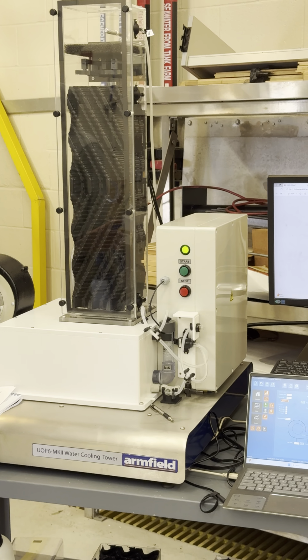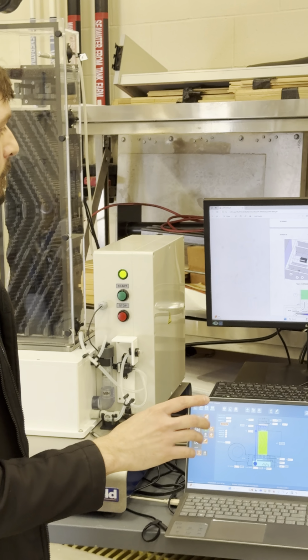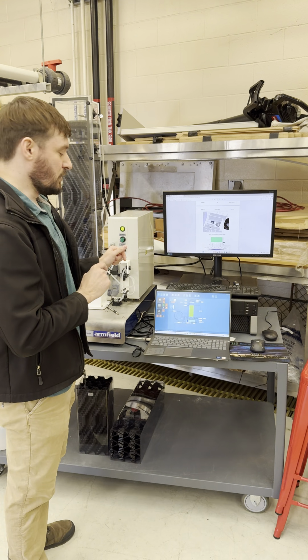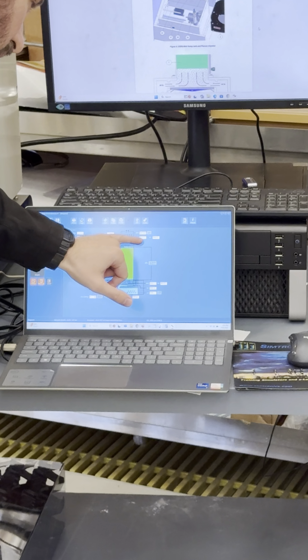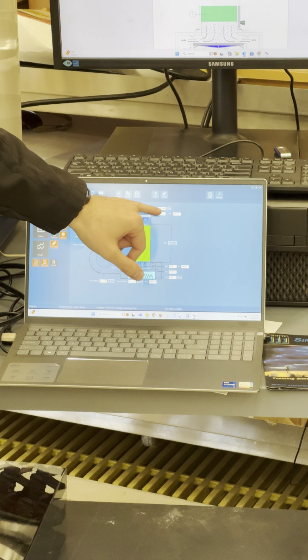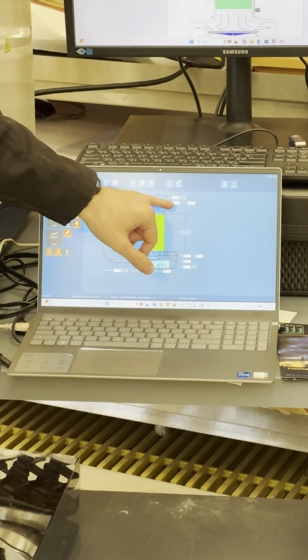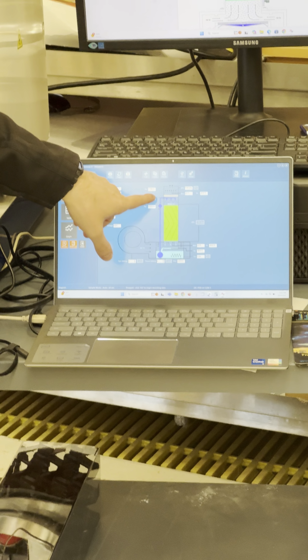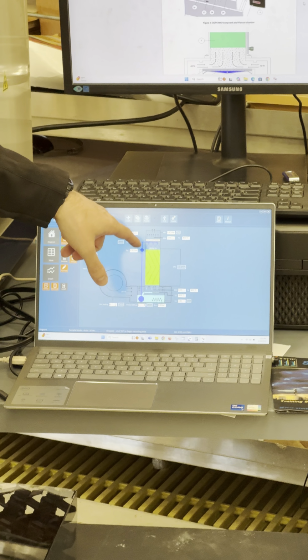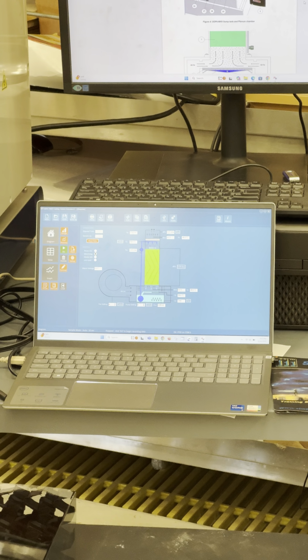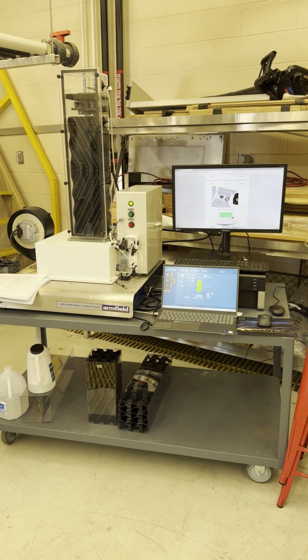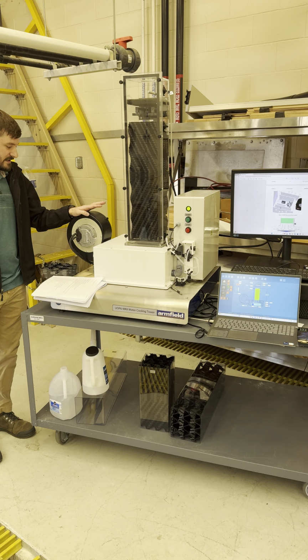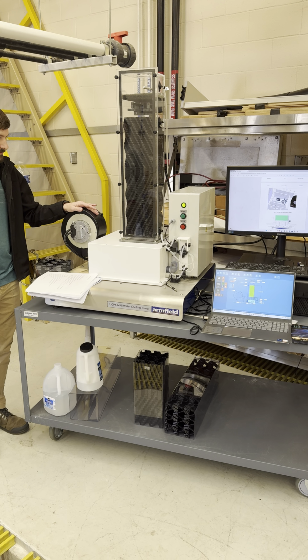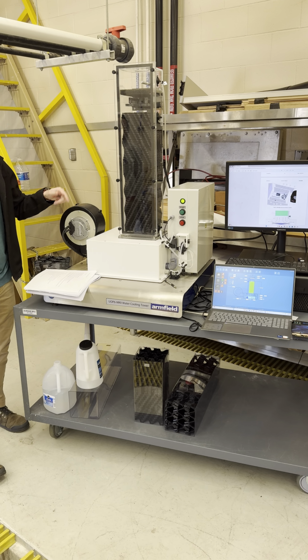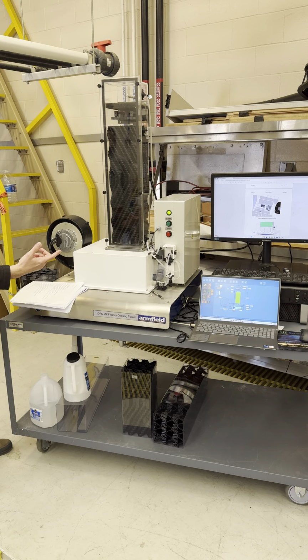So we're determining the airflow rate based on the differential in pressure. The unit does it. You can set the DP that it's looking for, the difference in pressure, and it'll output the flow. So you just need to kind of play with it until you get whatever you need. Okay. So we can set our fan speed, pump speed, and we can set the temperature and stuff like that.